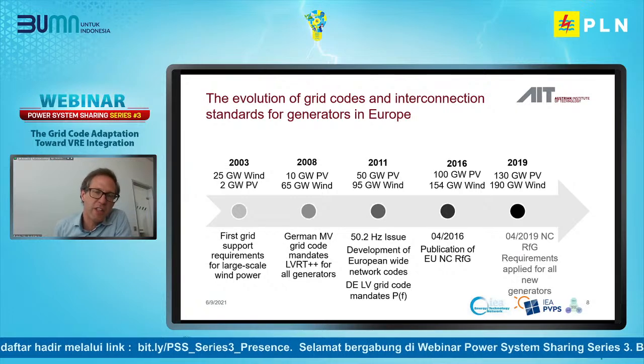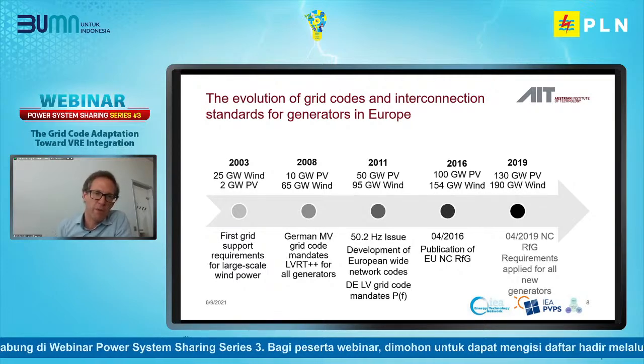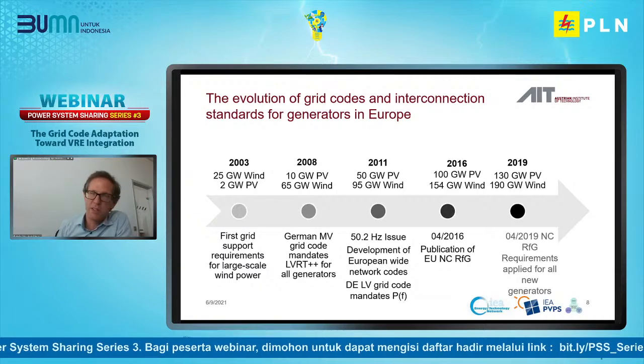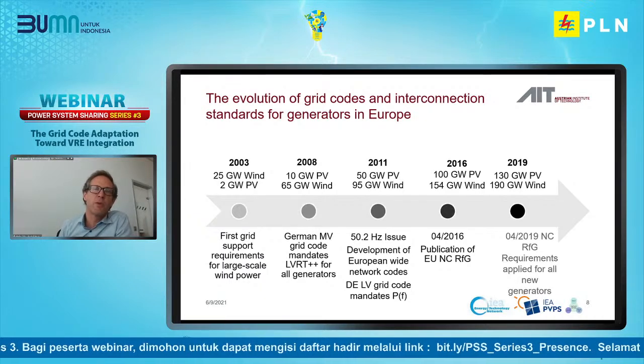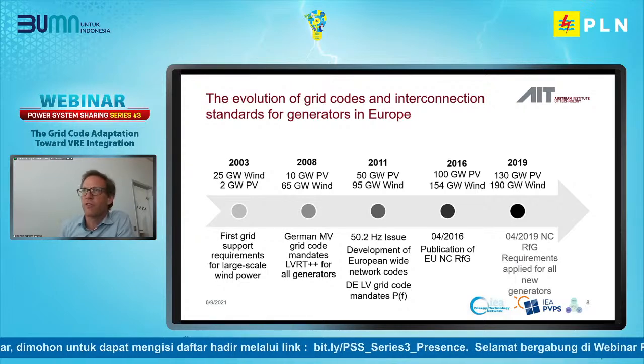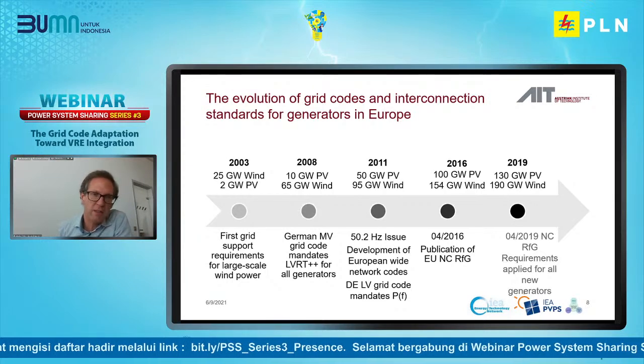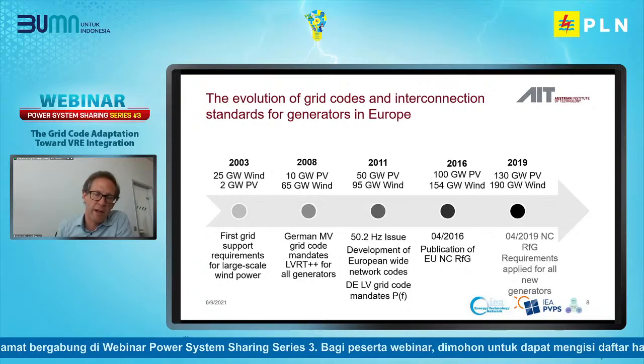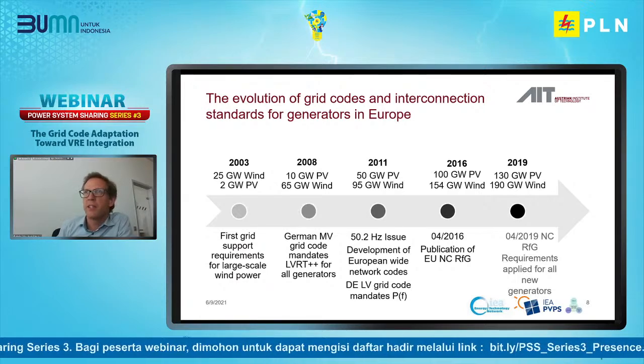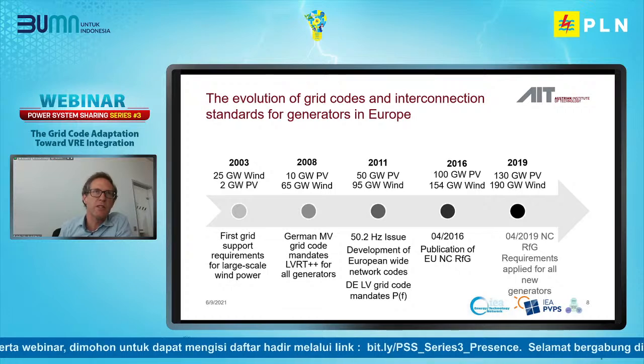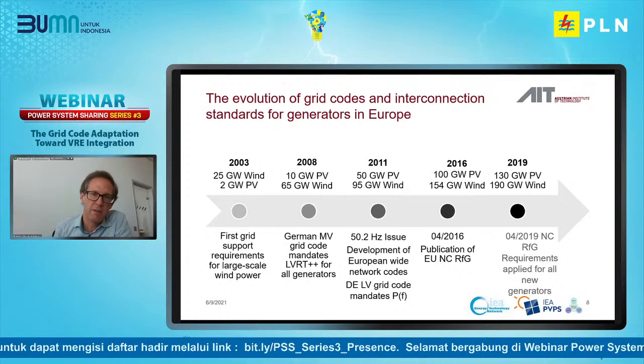A specific trigger was the so-called 50.2 Hertz issue, first discovered in Germany. At that time, a major paradigm change happened in Europe: it was realized that in order to maintain frequency stability in a system with a major share of non-synchronous, variable renewable-based generation, you need all generators, even very small-scale ones, to provide frequency support. At that time, the drivers were mainly in specific countries and markets where renewables already played an important role.